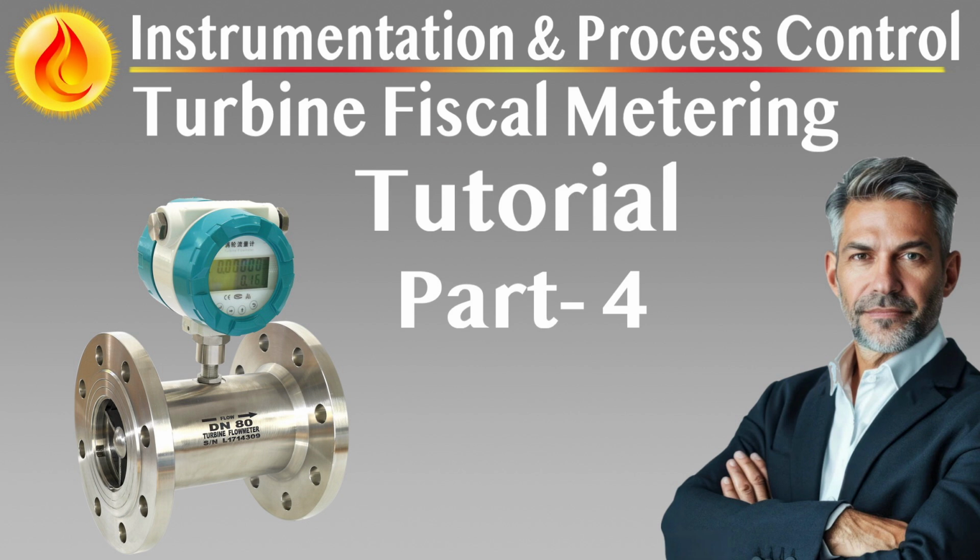Each junction box, termination point, and instrument housing must be verified for correct assembly, proper sealing, and compliance with hazardous area requirements. Explosion-proof and intrinsically safe devices must include documentation confirming compliance with hazardous zone classifications. Cable segregation, grounding systems, and earthing points must be inspected to ensure electrical safety and system reliability.